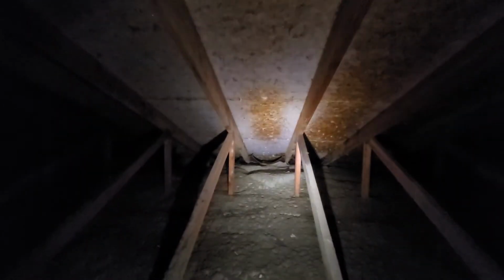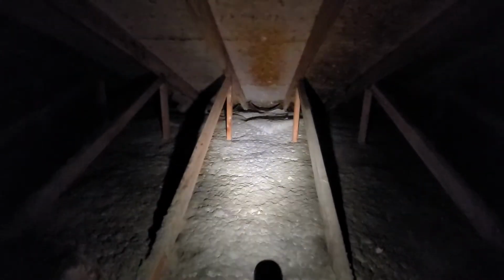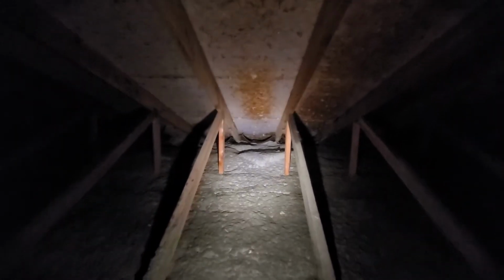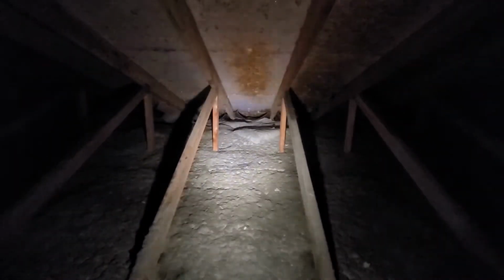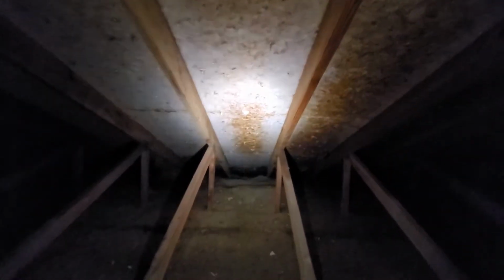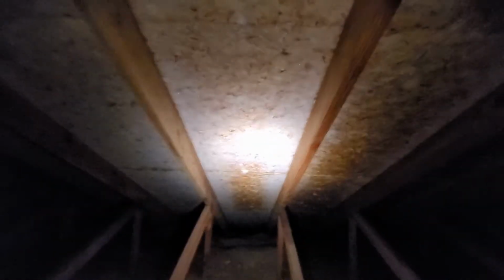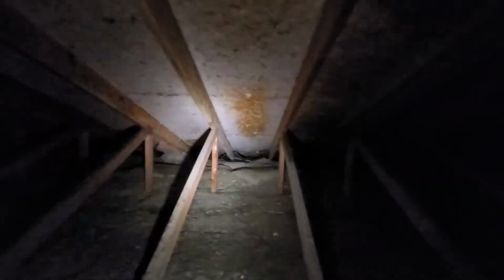To prevent it, what you have to do is move the air. You want the air that's coming off the top of the insulation, let's say it's 2 degrees above zero and it's minus 15 in the attic, you want to try to cool that air that's coming through the insulation before it touches here. If you can cause the condensation to form basically between the two and not on the sheathing, that's best. The best way to do that is to have air moving through the attic space.